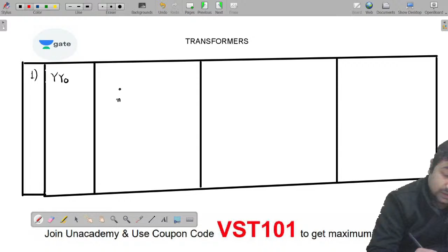Let me draw one more. Now please observe here. The first one is the star-0 connection. For star-0 connection, first take a neutral point, then draw a 12 o'clock position as HV A phase, and 120 degrees apart from this draw B phase, and 120 degrees apart from this draw C phase, keeping the phase sequence A, B, C.